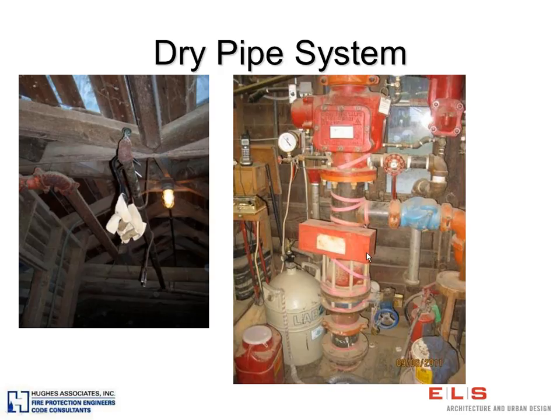You'll note, for those of you that have seen fire protection systems, you usually see wet pipe systems out there. And on a dry pipe system, there's a lot of junk that goes along with it. So there's a much bigger space requirement that a dry pipe system would take up. This is a big dry pipe valve here. These lines off to the left are going to a compressor to serve the dry pipe air, because what happens, I'll wait till I get to another slide, but what happens is that from here down the pipe is wet, and from here up the pipe is dry. So the room that this whole assembly sits in is in fact a heated room, because we do have water in this pipe that's running up to this point.